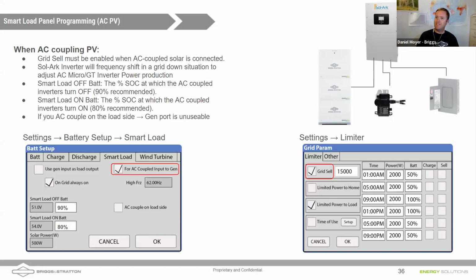Yeah, that's a good point. In a grid up situation, so if the grid is there and you have a grid connected system, as you will if you have a grid tie, if you're doing AC coupled solar, right? And you have this box checked, then the AC coupled solar is always on as long as the grid's there. But in a grid down situation, Daniel, you clarified it perfectly. As long as the battery is below 80%, the solar will always be on. And then as that battery starts to fill up and gets above 80%, it's still on until it reaches 90%, and then it would turn off. And that's to just make sure we don't overcharge our batteries. Yep.